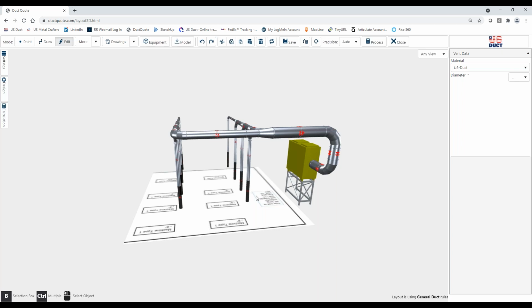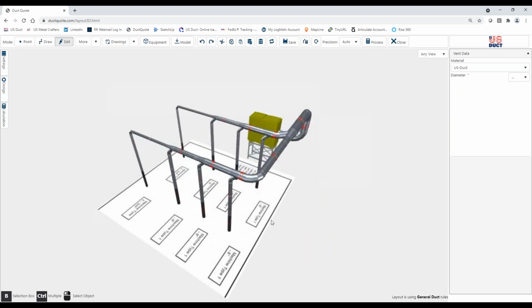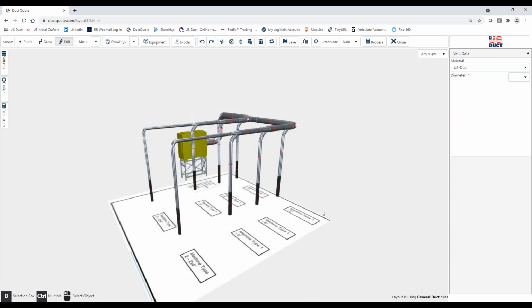Now, a big note here. If you've got 8 or more pickups, or you can't determine the definitive order of adjustments to be made, you can make pressure readings at each pickup point to confirm that they have similar readings. As you might imagine, doing this manually can take a great deal of time, especially knowing that as we change one of these pickup points' restrictions by changing the settings on our dampers or gates, we're going to have altered the situation for all of the other pickup points as well. So it does require a lot of moving back and forth to make sure things are right.